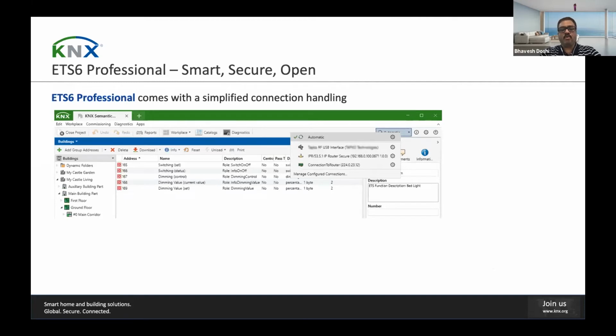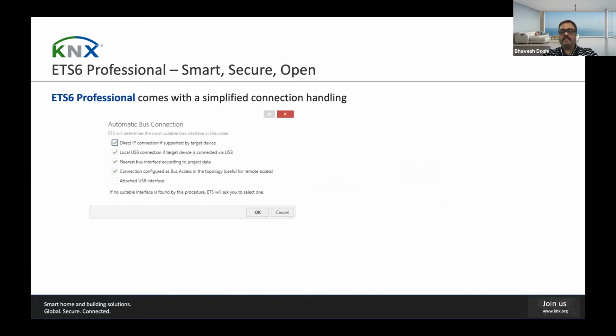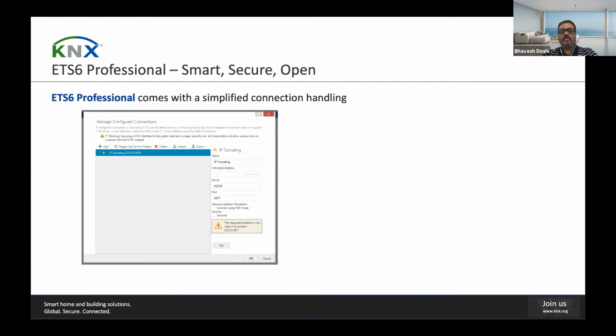The bus connection has always been project related, and its configuration has always been the first task of an installer when the project design has been completed in ETS. So ETS6 comes with a new simplified and completely redesigned bus connection handling that automatically finds and picks up the best suitable bus connections for a given project at a given moment. In this way, the installer does not have to manually configure any bus connections prior to commissioning. ETS6 does the job without bothering the installer. However, if the installer wants, he can configure the automatic discovery or still manually create, import and export bus connections.